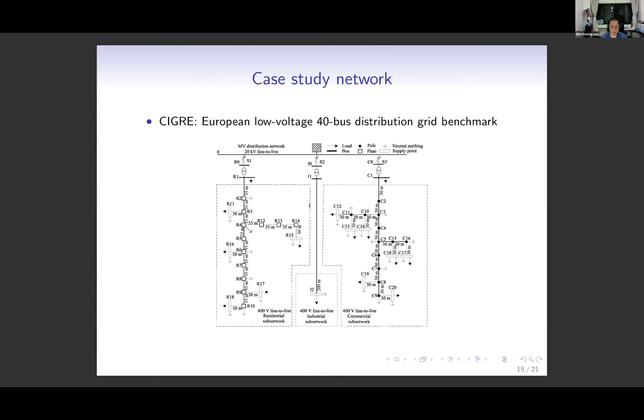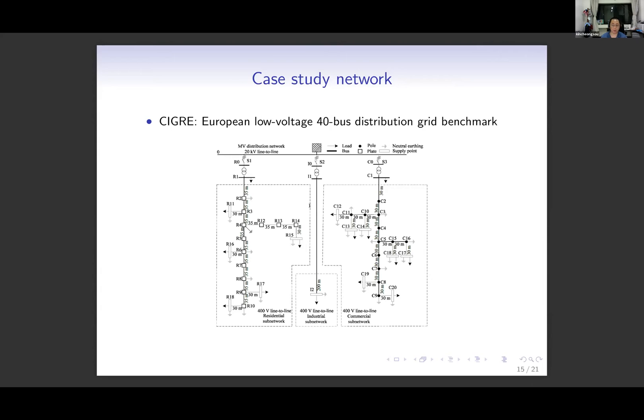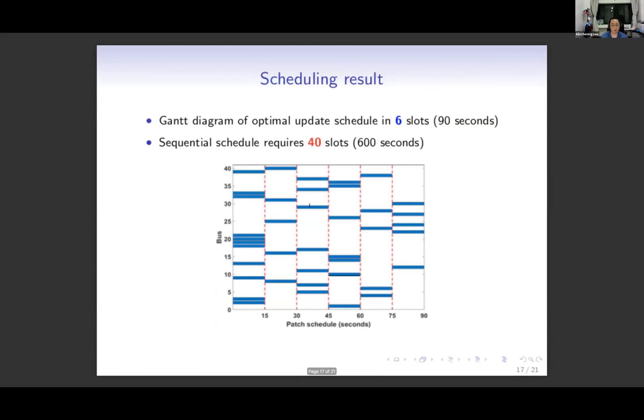Our case study uses the CIGRE 40-bus system. We assume all 40 buses have smart inverters requiring software updates. We solve different instances of our scheduling problem — our bin packing problem — with different values of H, the matrix describing voltage disruptions, to examine the effect of different levels of seriousness of update failure. The larger H, the more serious the failure. The update schedule obtained by solving our proposed integer program uses only six time slots to schedule all 40 updates, compared to 40 time slots if we sequentially scheduled updates.